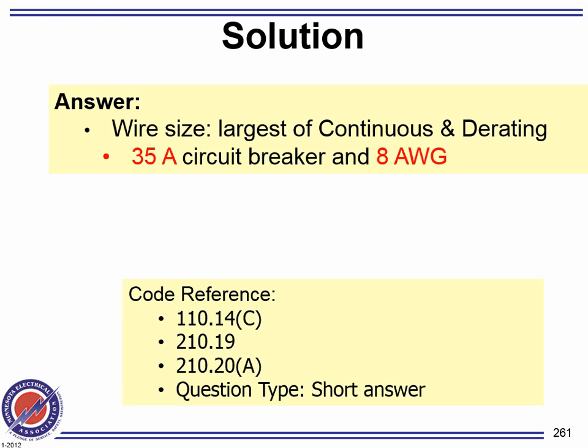How about your breaker? The only thing that sizes your breaker is the continuous load or non-continuous load. The derating has nothing to do with your breaker.